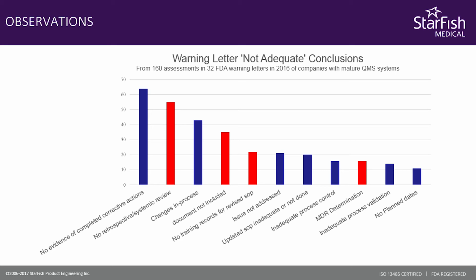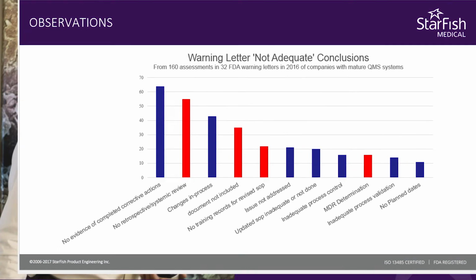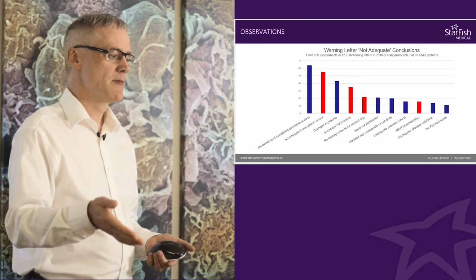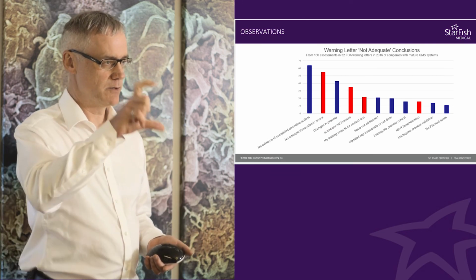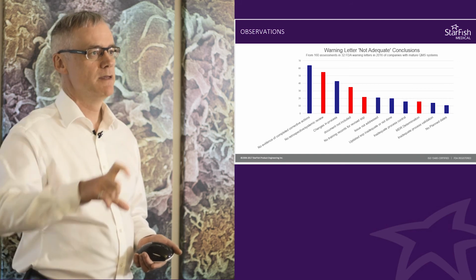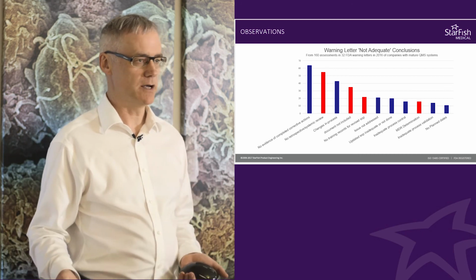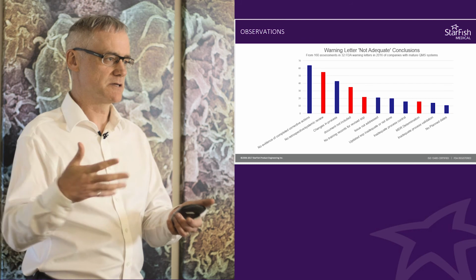What was the finding? The number one reason was that no evidence was supplied that you had actually completed the corrective action. That was cited in over 60% of the cases. Maybe you actually hadn't completed the action yet, but that's very common. And maybe you only have a short period of time to respond, so you can't always address everything. That one I didn't highlight as a killer, because maybe you just haven't had a chance to deal with it yet, and you're going to get a warning letter because they caught you doing something that's going to take a while to fix.